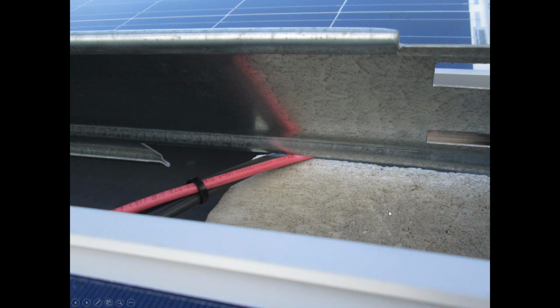They're great because there's no roof penetrations. However, you do have added weight to the roof, so our structural engineers would need to get involved. But also, we need to consider they're abrasive, and we need to consider protecting these conductors against these abrasive edges. One of the things to think about with PV systems is they don't only need to last today or tomorrow, but also these are going to be installed for the next 20 plus years. So will this installation method hold up? That's what we think when we look at these installations.